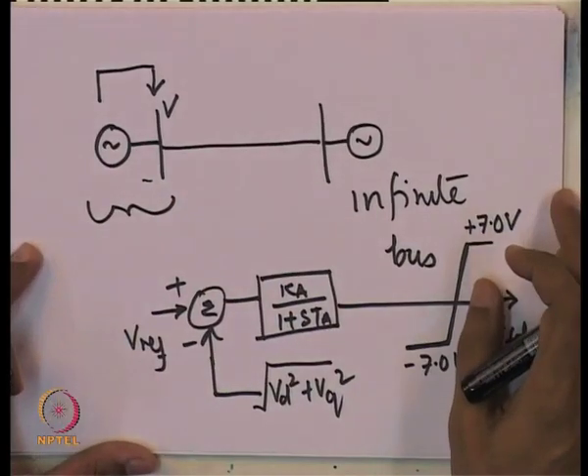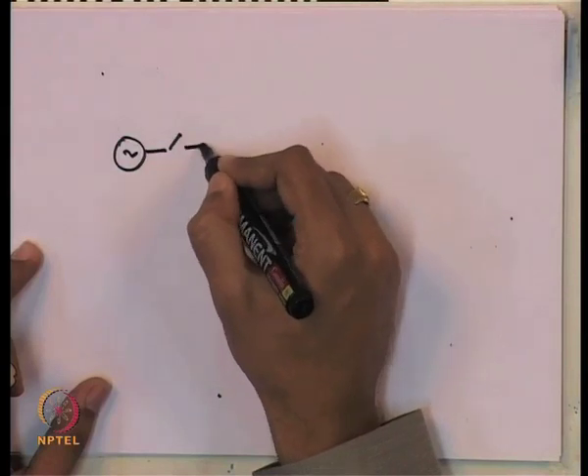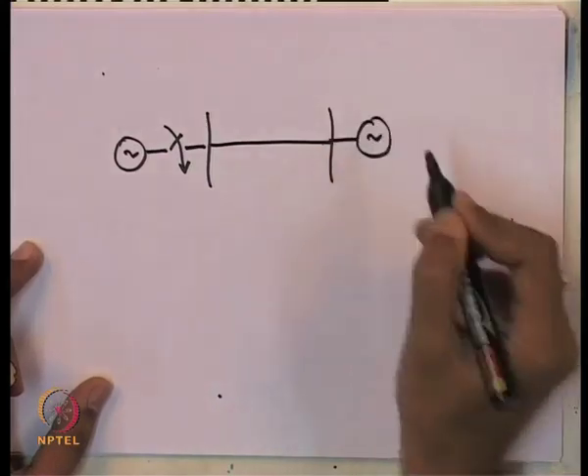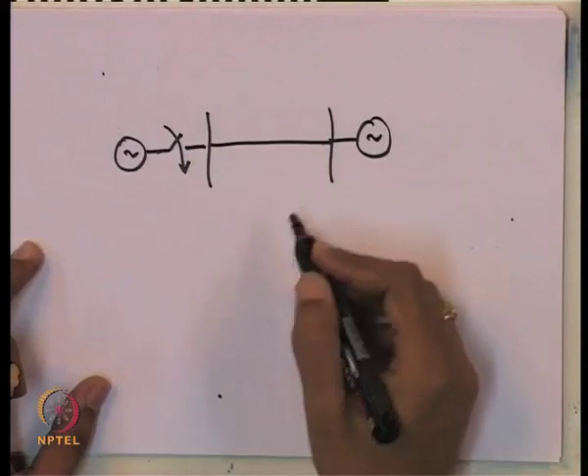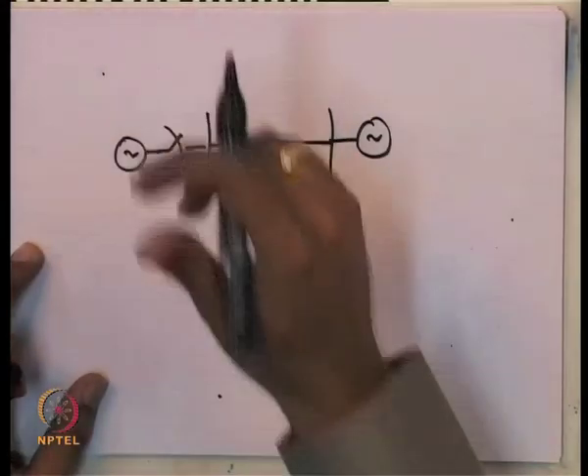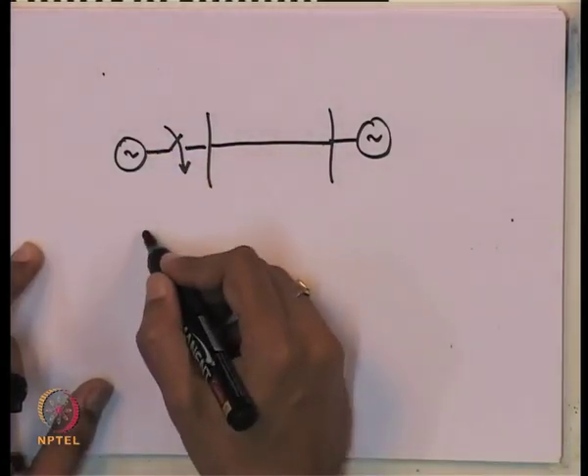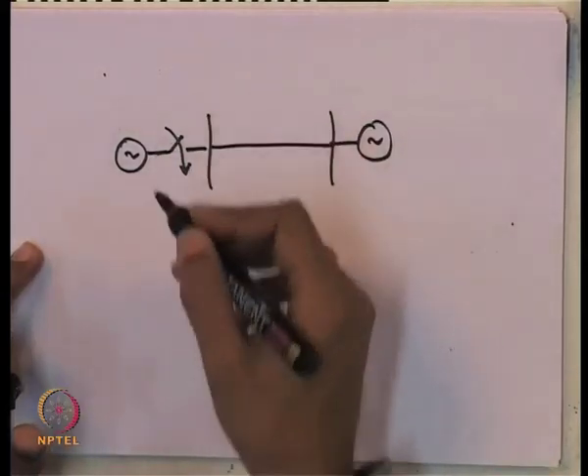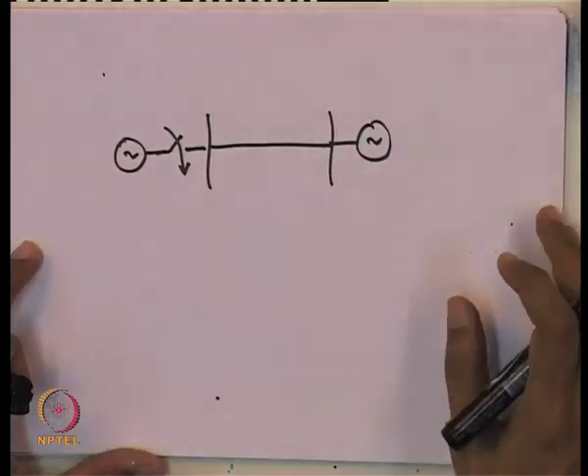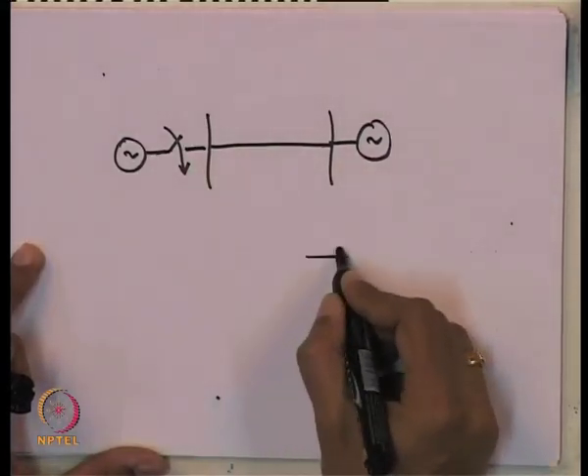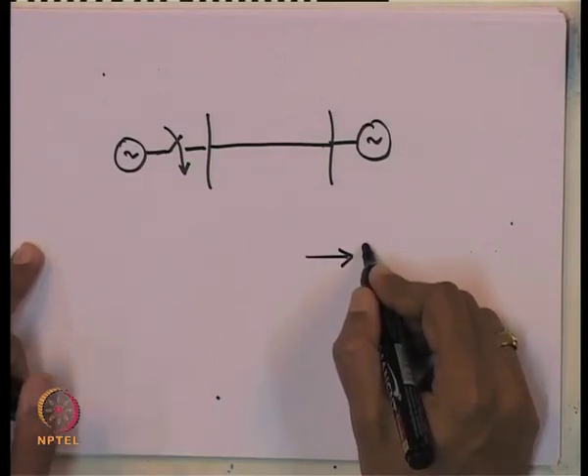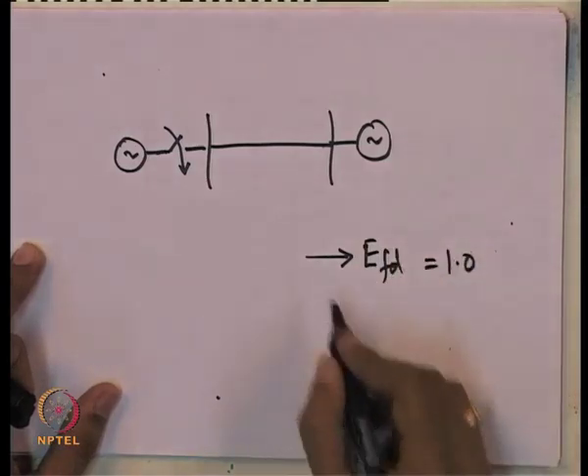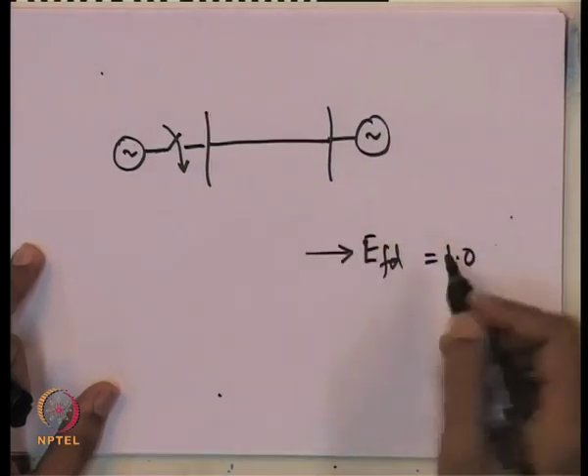The simulation is carried out in the following steps. First, the synchronous machine is synchronized to the voltage source — it is a bumpless synchronization. Initially, the power is zero at the time of synchronization, the open circuit voltage is 1 per unit, and the machine is running at practically rated speed. In order to create 1 per unit at the terminals of the machine, you need Efd equal to 1.